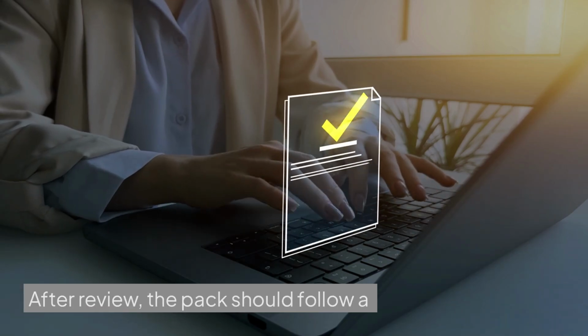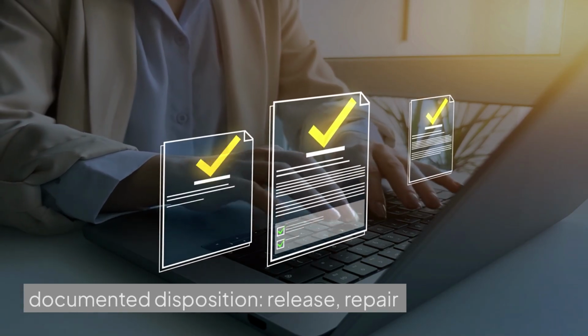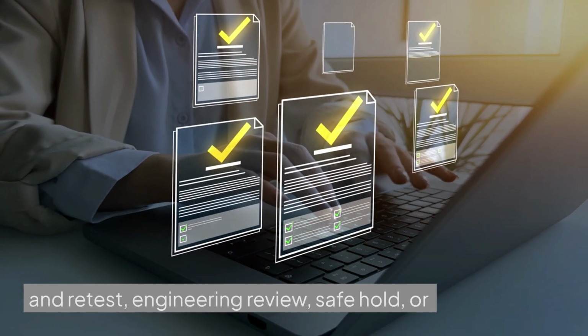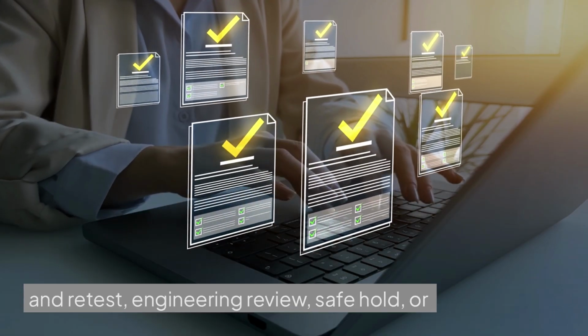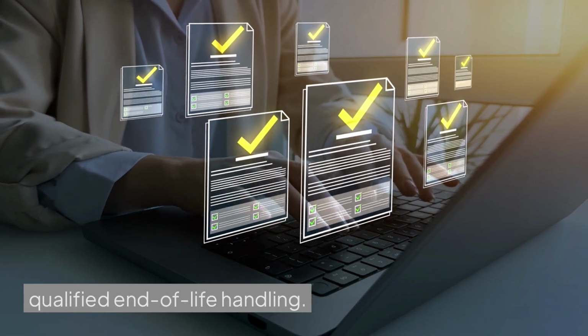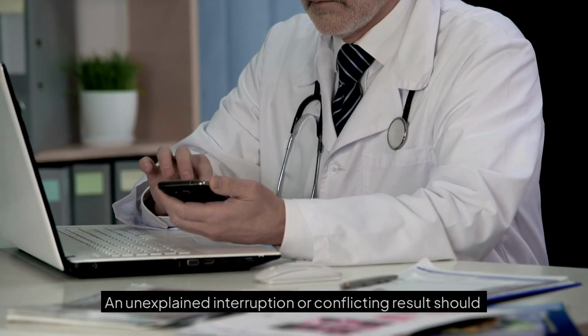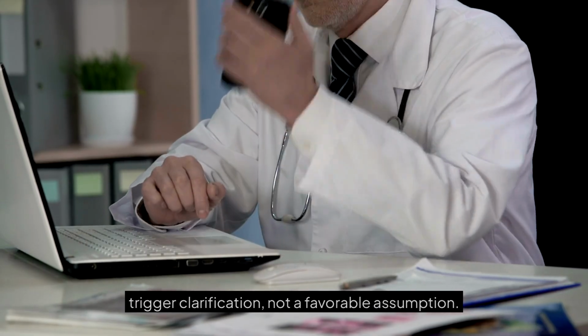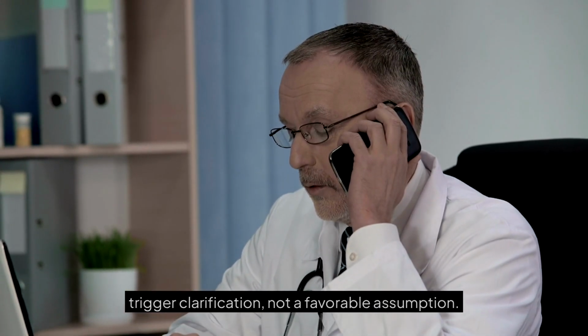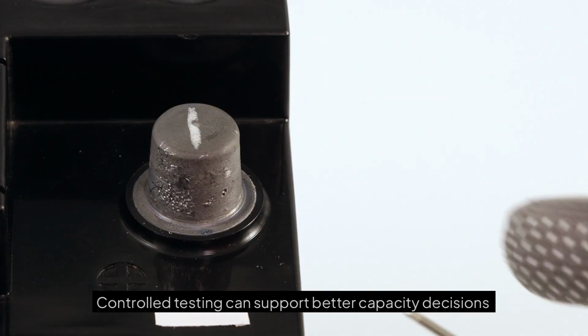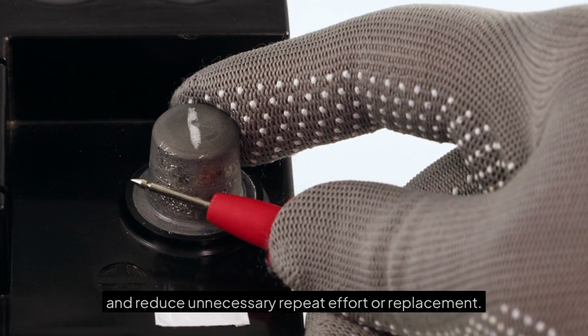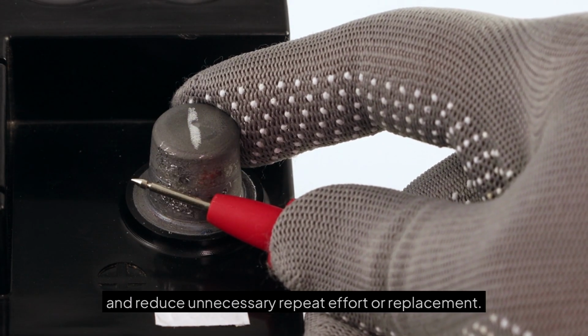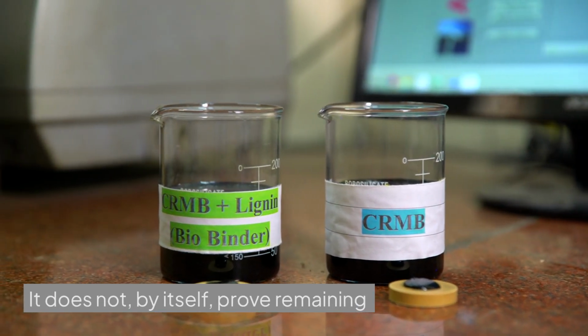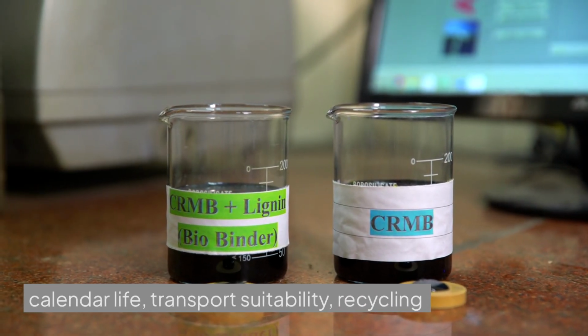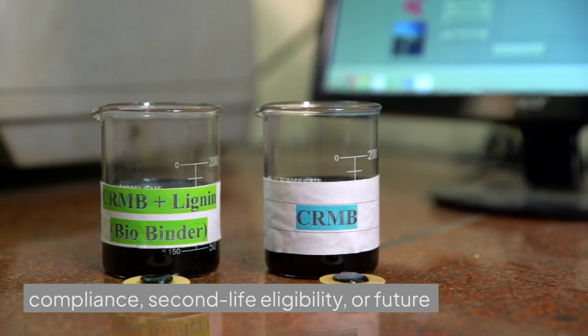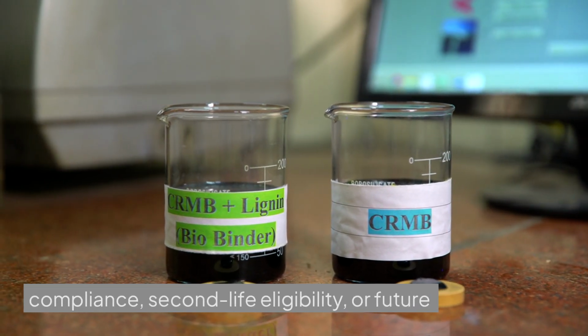After review, the pack should follow a documented disposition: release, repair and retest, engineering review, safe hold, or qualified end-of-life handling. An unexplained interruption or conflicting result should trigger clarification, not a favorable assumption. Controlled testing can support better capacity decisions and reduce unnecessary repeat effort or replacement. It does not, by itself, prove remaining calendar life, transport suitability, recycling compliance, second life eligibility, or future performance.